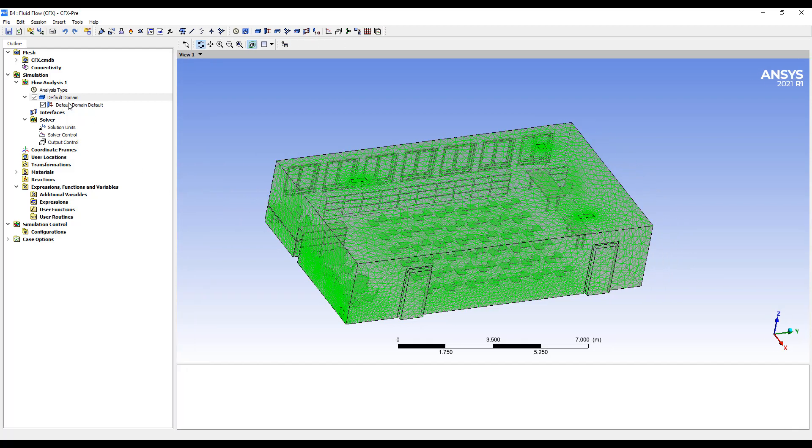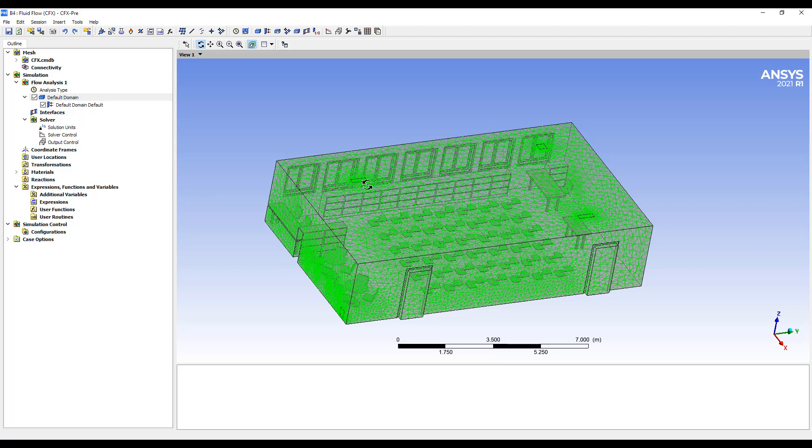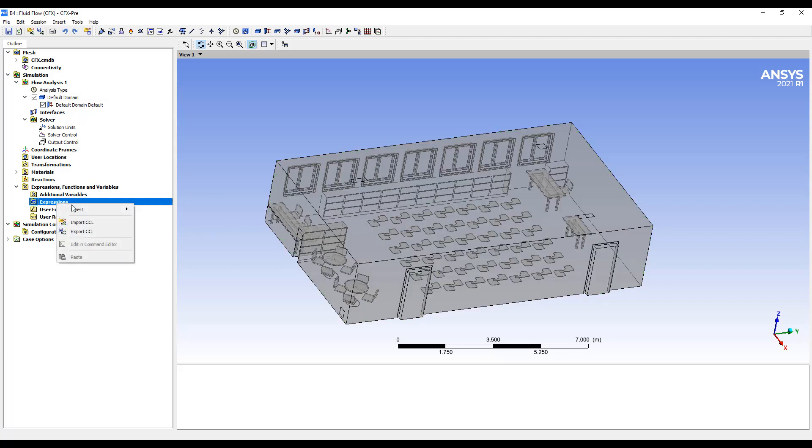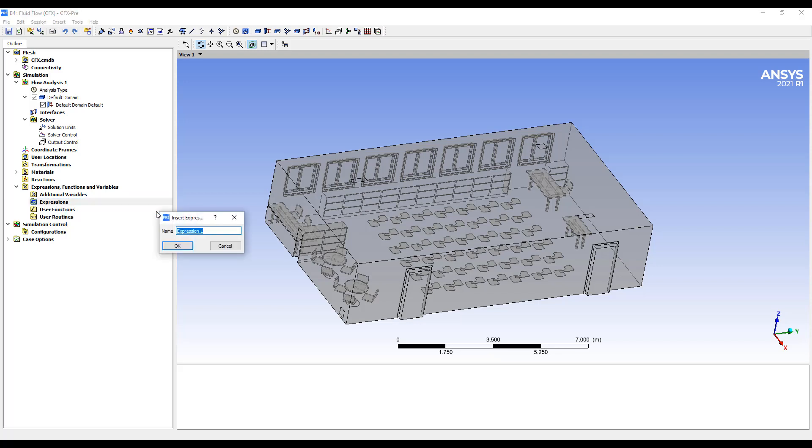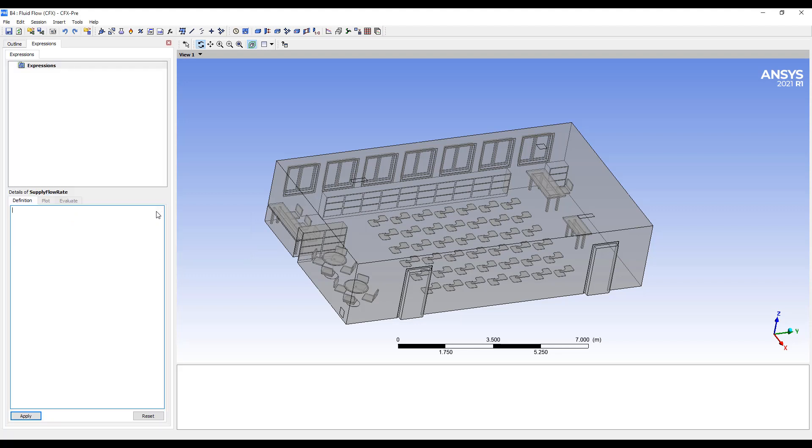Oftentimes, the flow rates in ventilation are specified in CFMs, cubic feet per minute. So let's call it supply flow rate. I usually create expressions for this. So supply flow rate. We have two vents here.